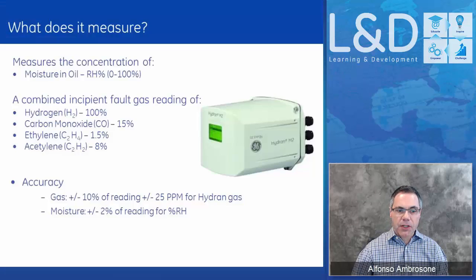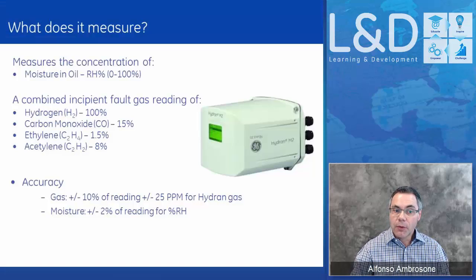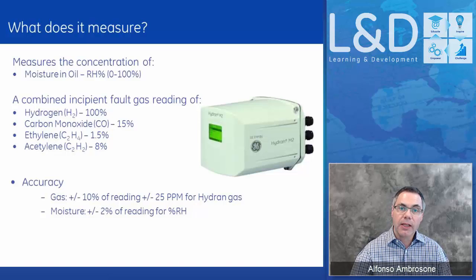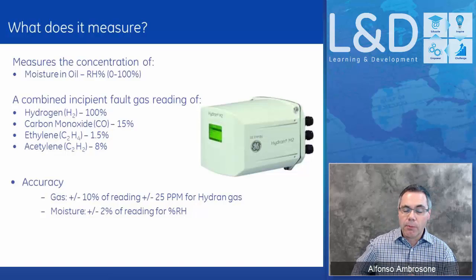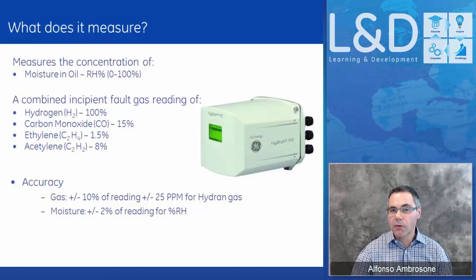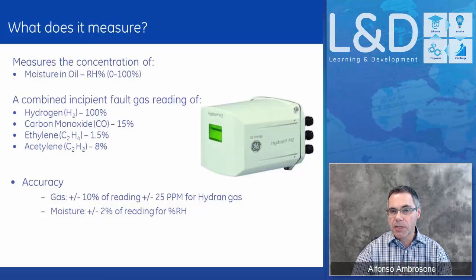Product specification features: the Hydran M2 measures moisture in the oil from 0 to 100% relative humidity, and that humidity reading is also calculated back into a PPM level for customers who prefer to work in PPM. Then we do the composite gas measurement, looking at hydrogen, CO, acetylene, and ethylene — each with their different sensitivities and concentrations.